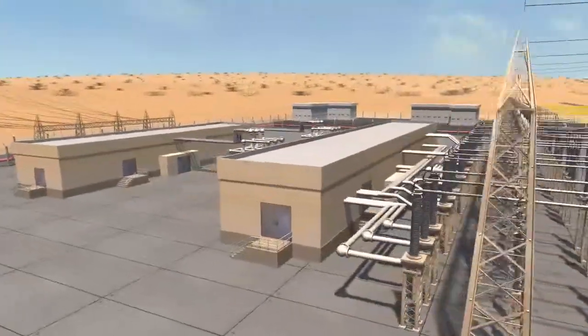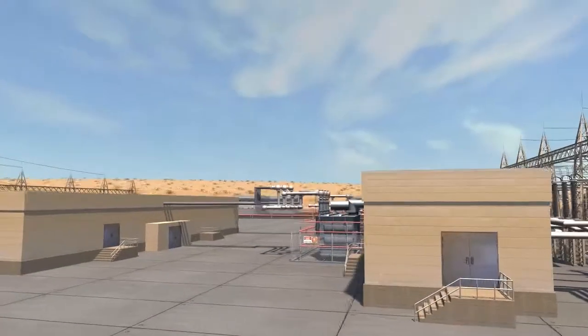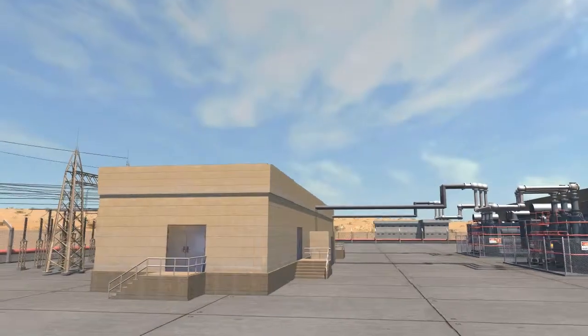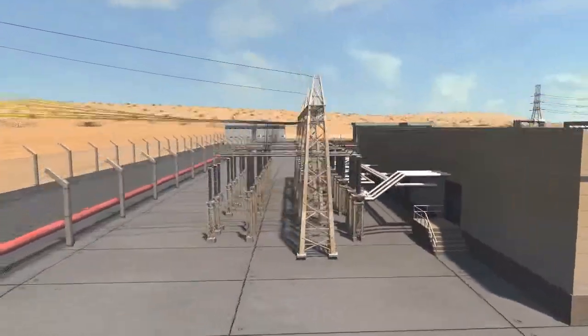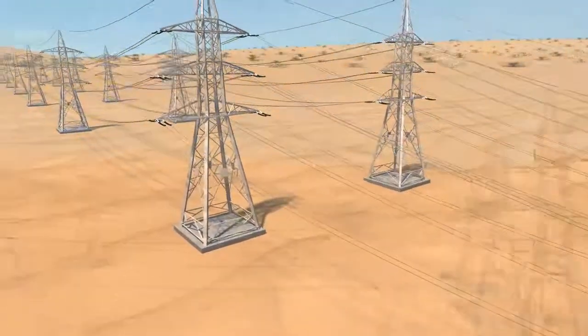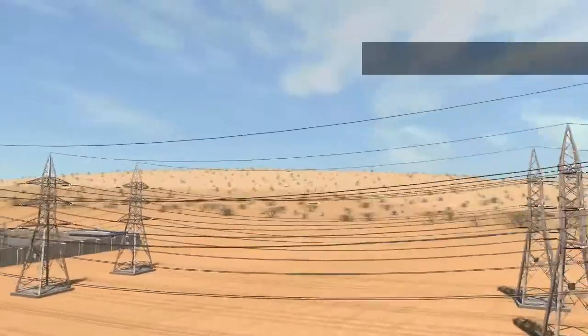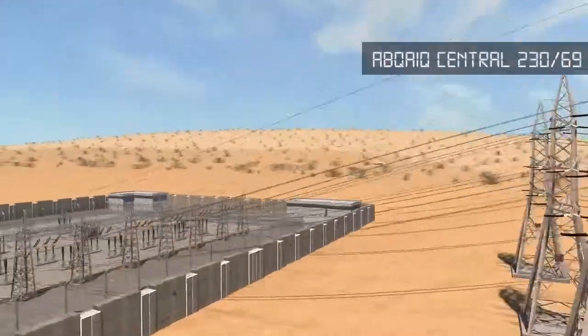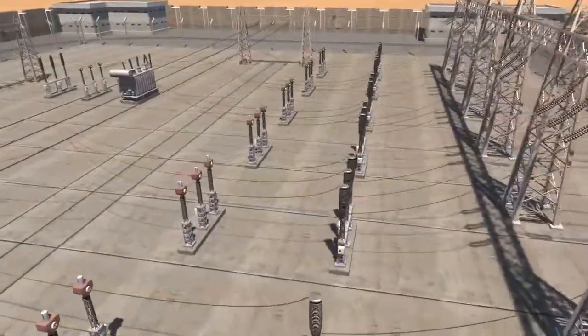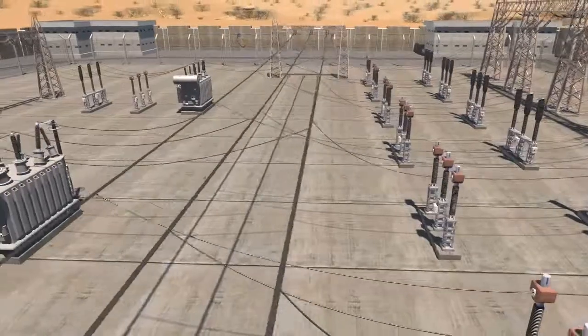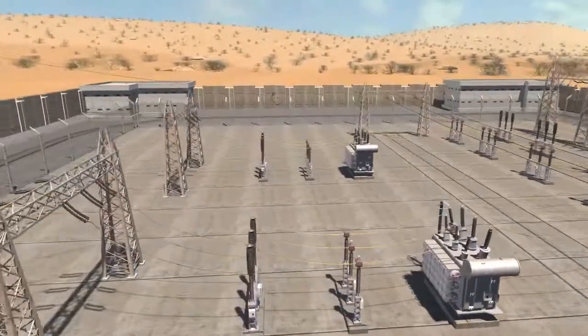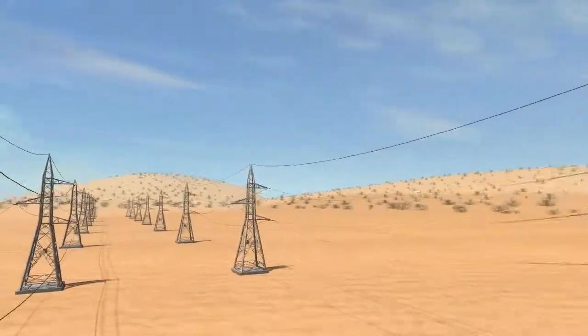Switching stations include bulk supply points (BSP) and grid stations. The 380 kilovolt or 230 kilovolt transmission voltage levels are mostly present in bulk supply points, which are located at the boundary of the city. The grid station receives 115 kilovolt or 69 kilovolt electrical energy through cables and steps it down to 13.8 kilovolt. Grid stations, which are located inside cities, are considered the final link in the transmission network.